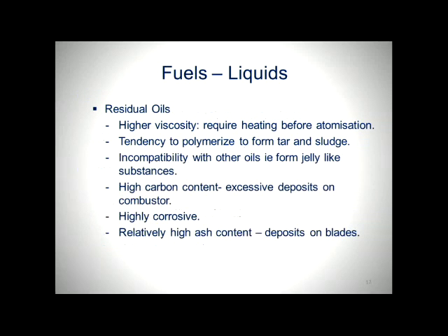Okay, we've also got residual oils, which means all the rubbish that you can't really do anything with. Hey, burn it in a gas turbine. But usually these residual oils are quite high viscosity, so they require heating before you can spray them in. They can polymerise and form tar and sludge, and a lot of the time they're incompatible with oils that you would use for lubrication. So if you get them mixed in with that, they can form jelly-like substances.